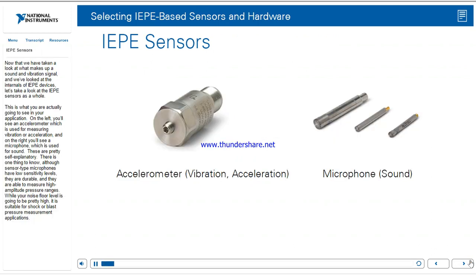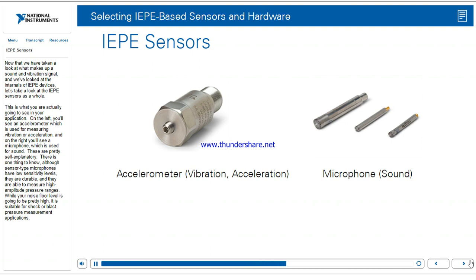Now that we've looked at the internals of IEPE devices, let's look at the IEPE sensors as a whole — what you're actually going to see in your application. On the left you'll see an accelerometer, used for measuring vibration or acceleration, and on the right a microphone, used for sound. One thing to note: although sensor-type microphones have low sensitivity levels, they're durable and able to measure high amplitude pressure ranges. So while your noise floor level is going to be pretty high, they're suitable for shock or blast pressure measurement applications.